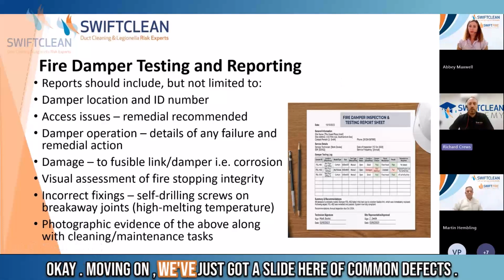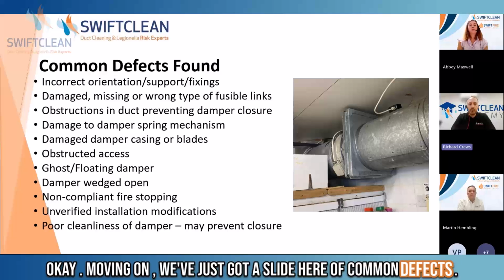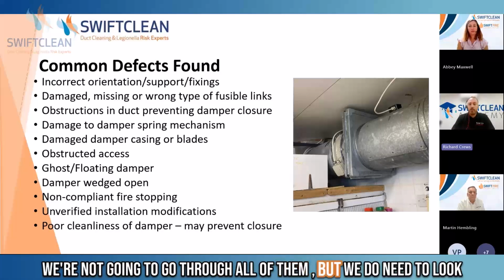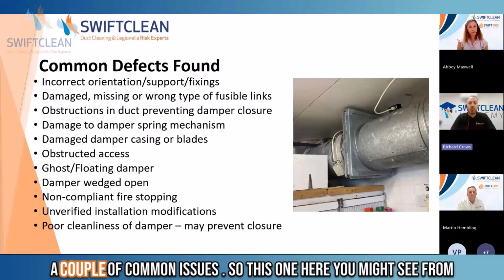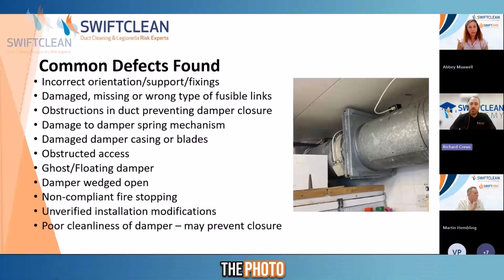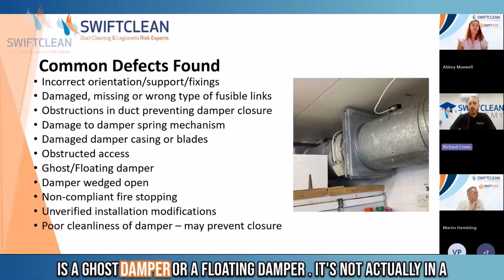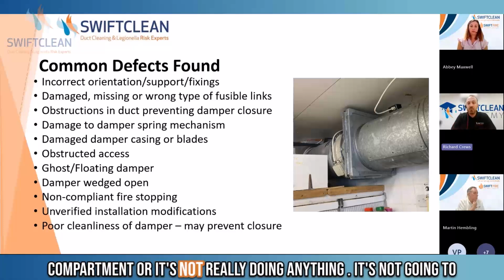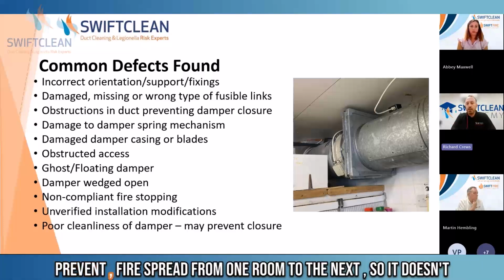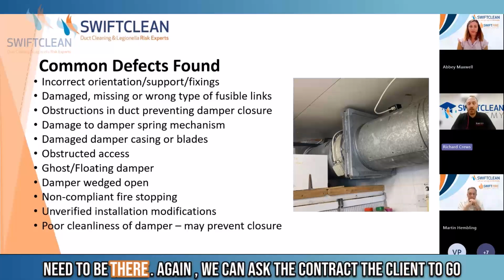Okay, moving on, we've just got a slide here of common defects. We're not going to go through all of them, but we do need to look at a couple of common issues. So this one here you might see from the photo is a ghost damper or a floating damper. It's not actually in a compartment wall. It's not really doing anything. It's not going to prevent a fire spread from one room to the next. So it doesn't need to be there.